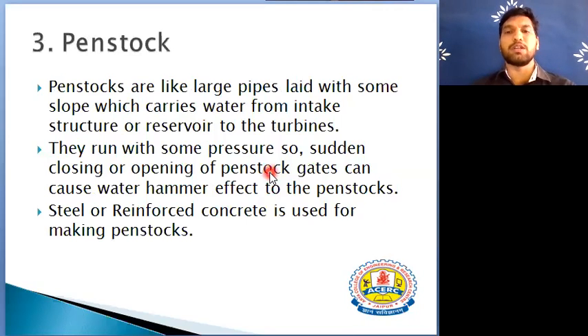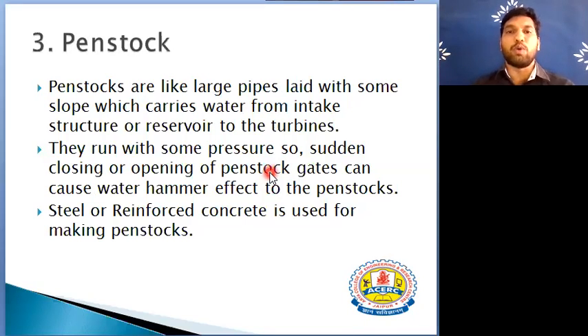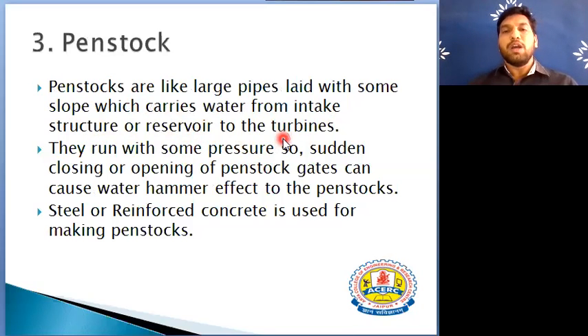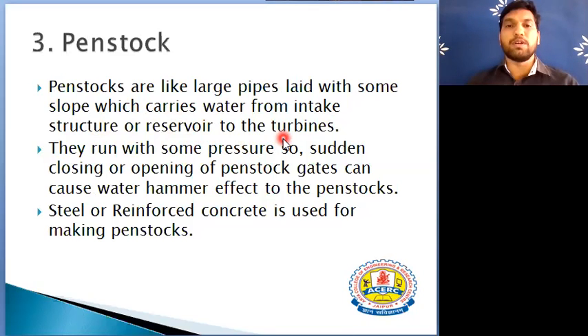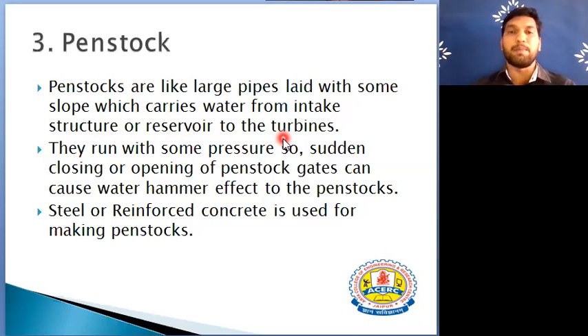The next component is the penstock. Penstocks are large pipes made up of steel and concrete which are used to convey or transfer water from the forebay or intake structure to the turbine. Due to the slope on which penstocks are fixed, the water pressure will be high. So if the gates of the turbine are suddenly closed, there will be high pressure in the water flowing into the penstock, and a water hammer condition may arise.